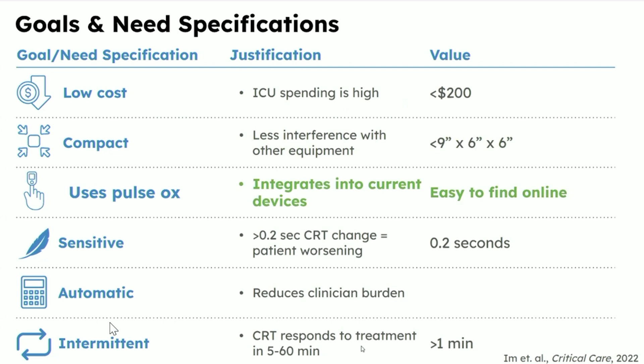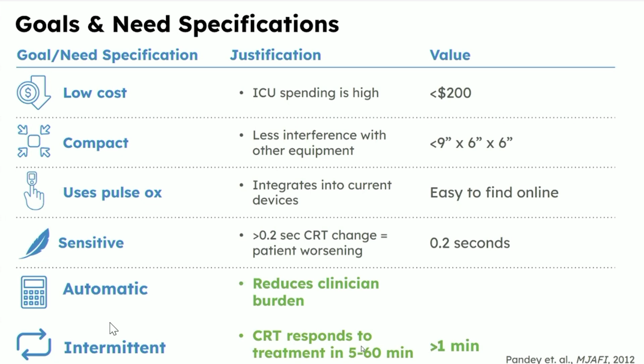Fourth, devices must be sensitive and track changes in patient CRT. Prime can detect 0.2-second changes in CRT. Lastly, Prime automatically takes intermittent measurements to reduce clinician burden and track changes in CRT over time. Prime can take measurements as short as every minute.